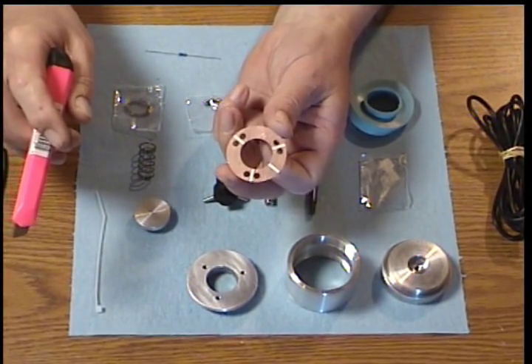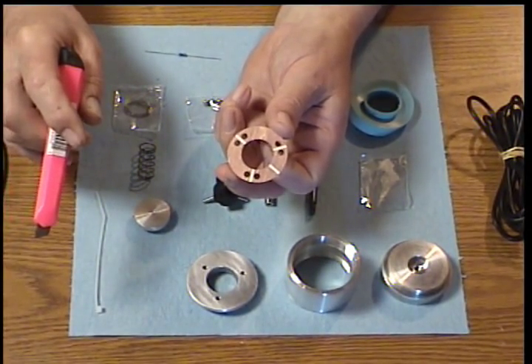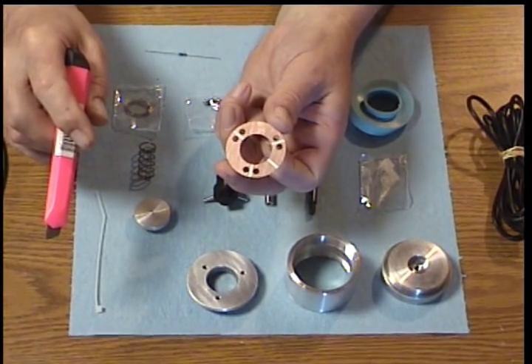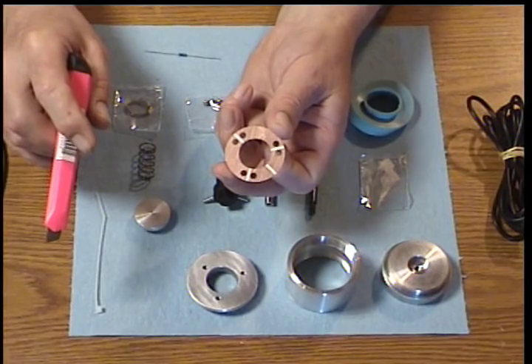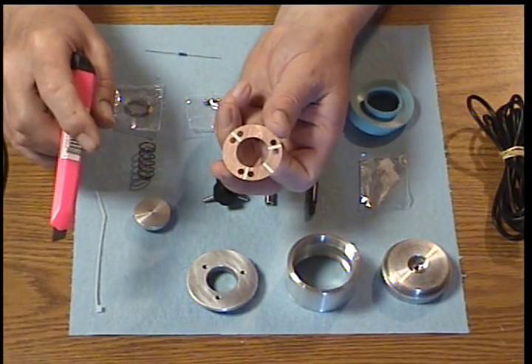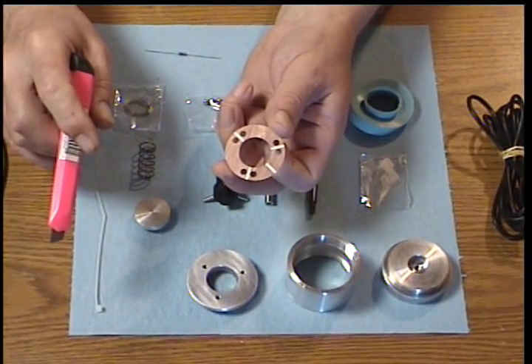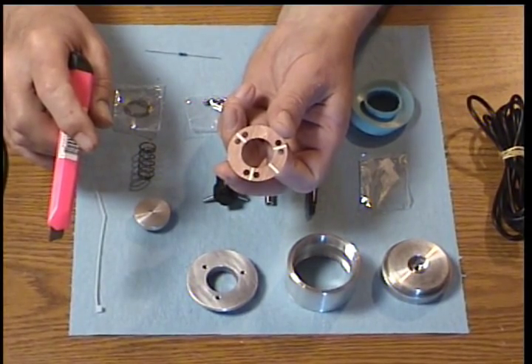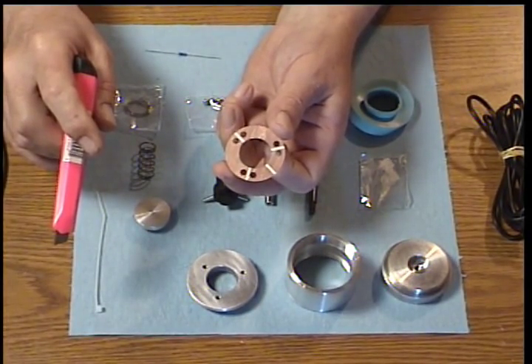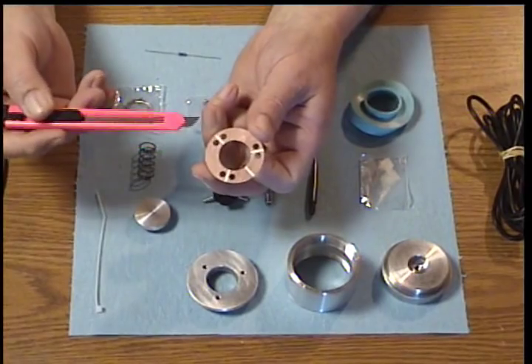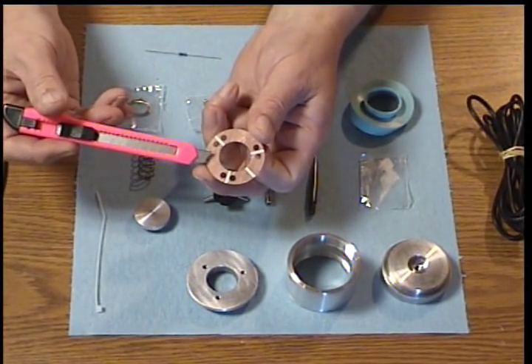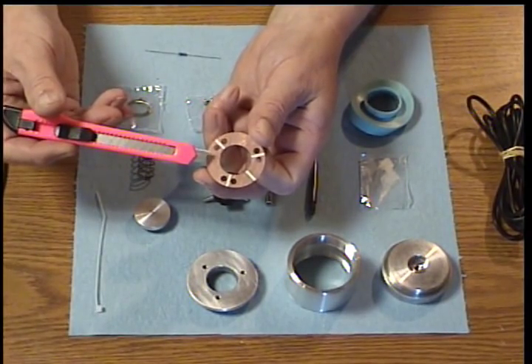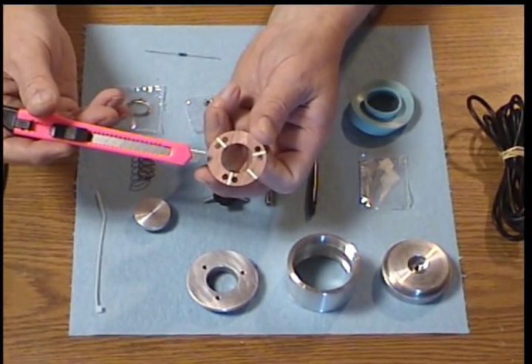Be very cautious if you do have to do any deburring that you do not enlarge the hole, deform the hole, or change its proportion and dimensions in any way. This would cause the balls that will be later soldered to the board to be out of relationship one to another and cause inaccuracies in the probe.